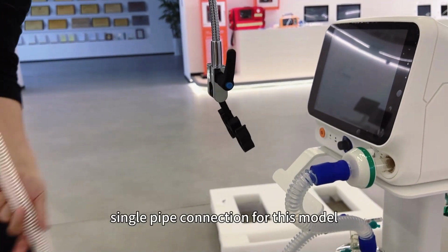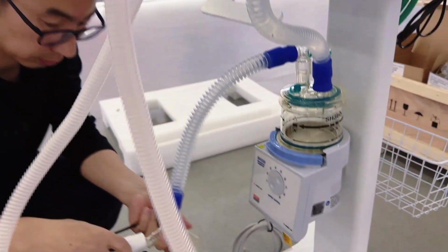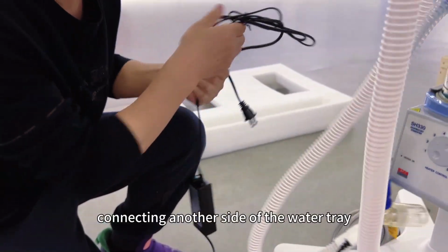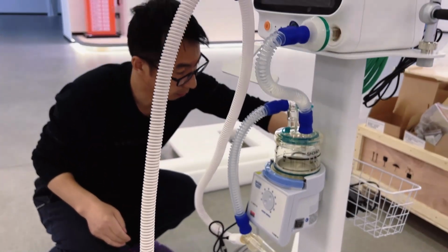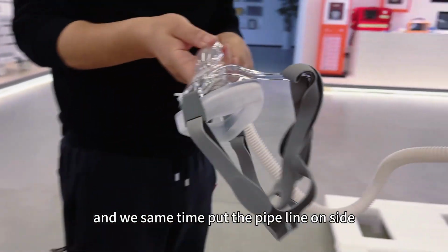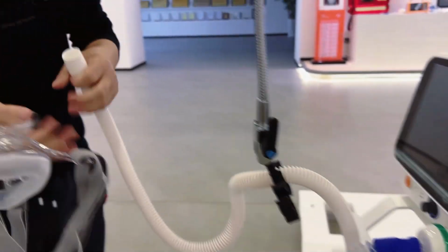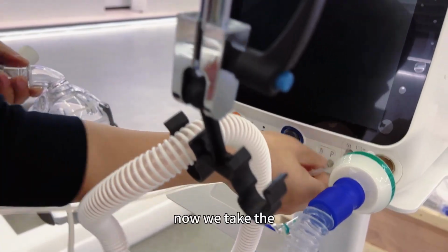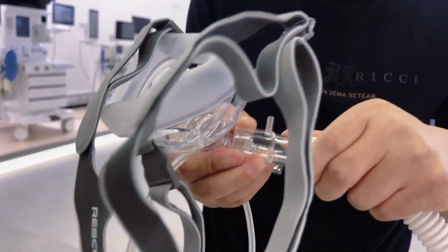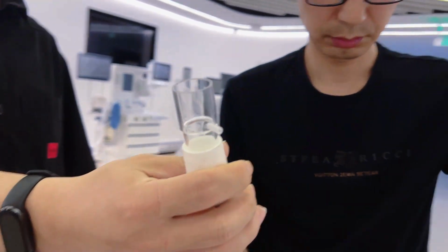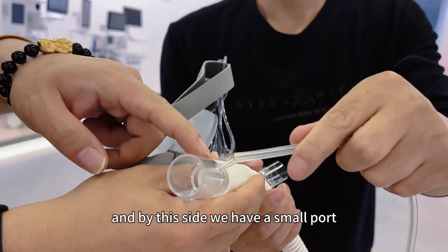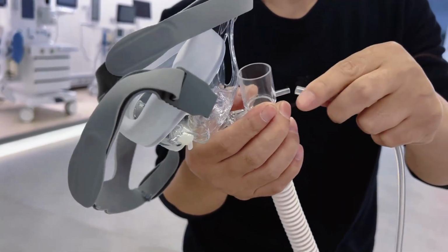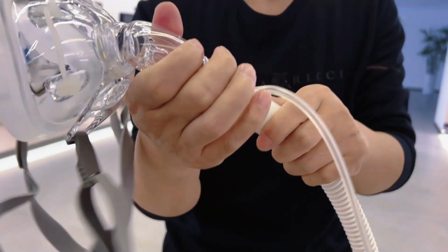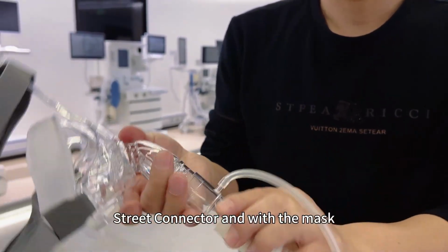Now we connect another short pipeline, one side with the humidifier connector, and then with the water trap. And this connection is the single pipe connection for this model. Now we take the non-breathing pipeline, connecting another side of the water trap. And at the same time, put the pipeline on the side of the holder so it does not hang down on the floor. Now we take the small pipeline, connect one side on the P port, which is for testing the pressure. And we connect the strict connector on this white pipeline. And by this side, we have a small port. We connect another side of the small pipeline. Then we connect it with the strict connector and with the mask.